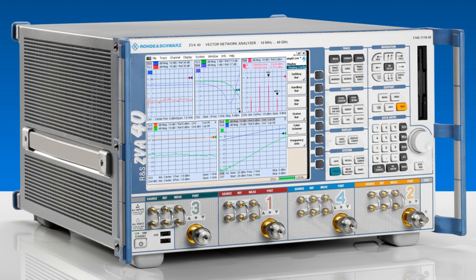The diagram shows the essential parts of a typical two-port vector network analyzer (VNA). The two ports of the device under test (DUT) are denoted port 1 (P1) and port 2 (P2). The test port connectors provided on the VNA itself are precision types which will normally have to be extended and connected to P1 and P2 using precision cables 1 and 2, PC1 and PC2 respectively, and suitable connector adapters A1 and A2 respectively. The test frequency is generated by a variable frequency CW source, and its power level is set using a variable attenuator. The position of switch SW1 sets the direction that the test signal passes through the DUT.